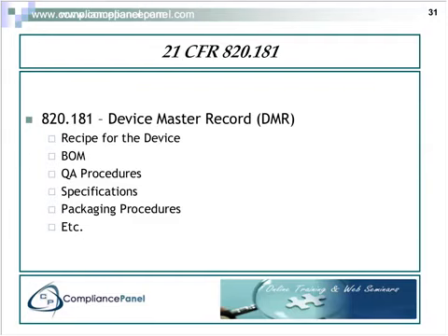And it's important to understand that each time a device's revision changes, the device master record also changes. It's required that we have a sound and documented methodology for creating, maintaining, and changing the device master record. Again, this methodology should be covered by a combination or a single operational document that's maintained by your organization.